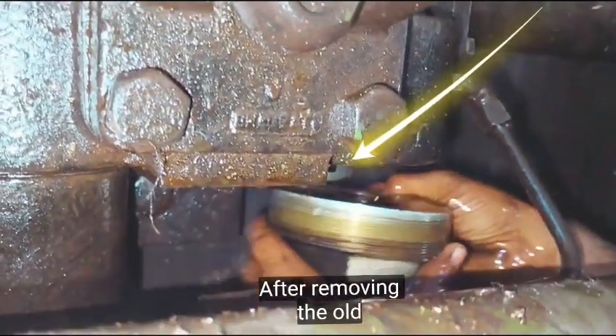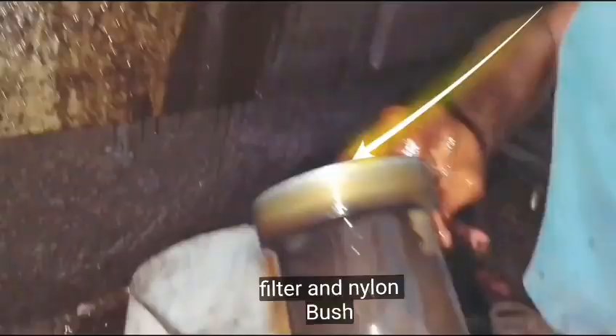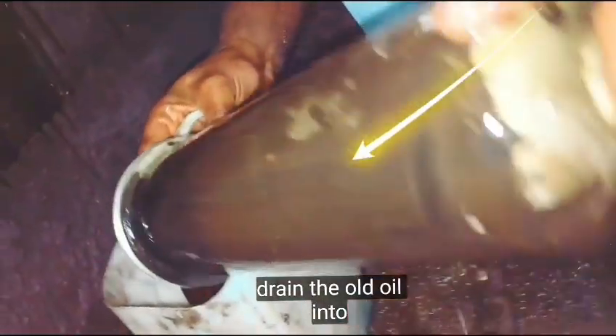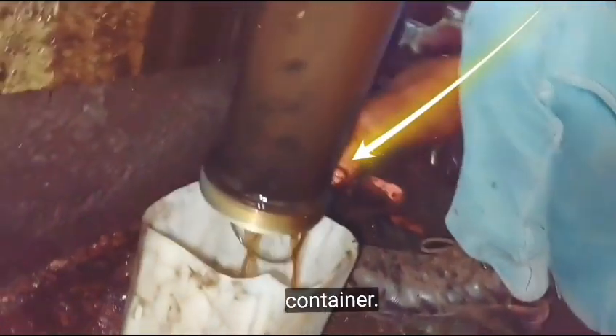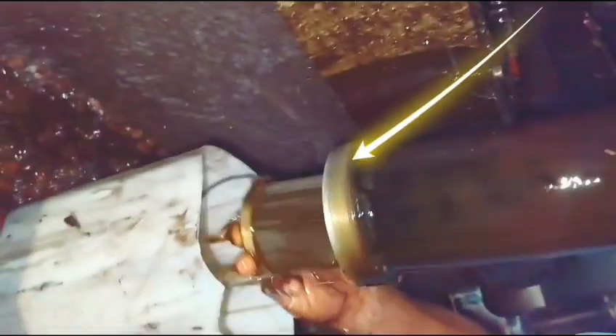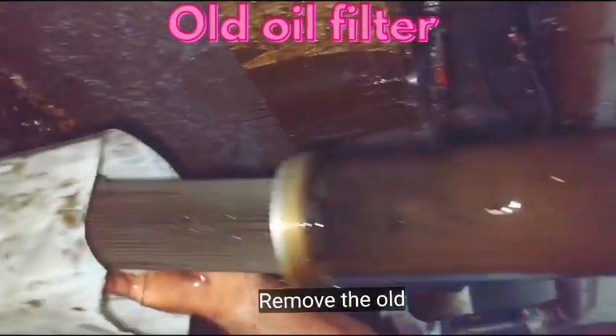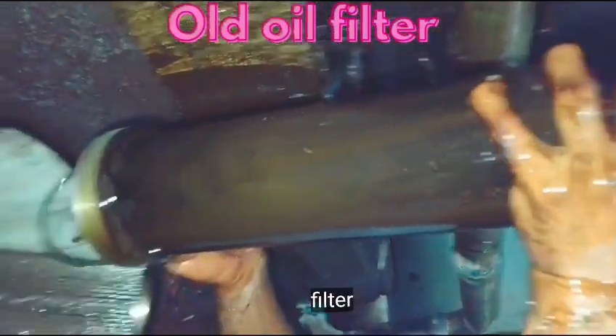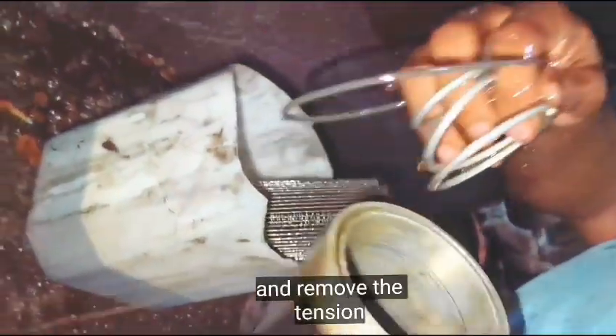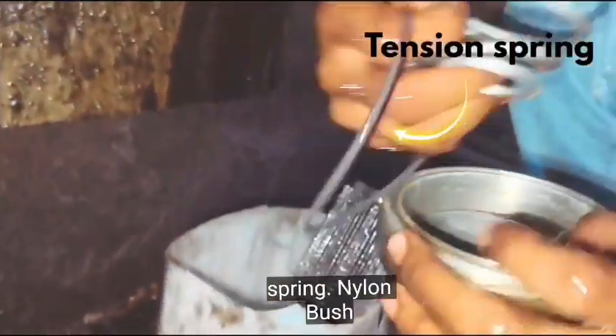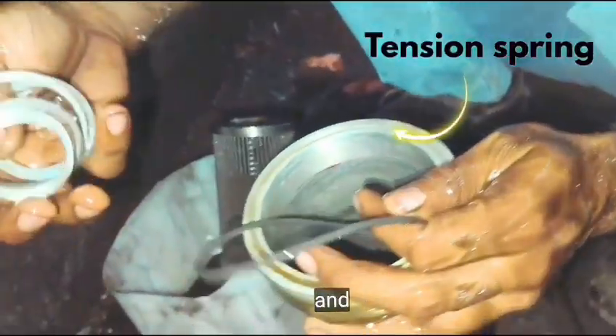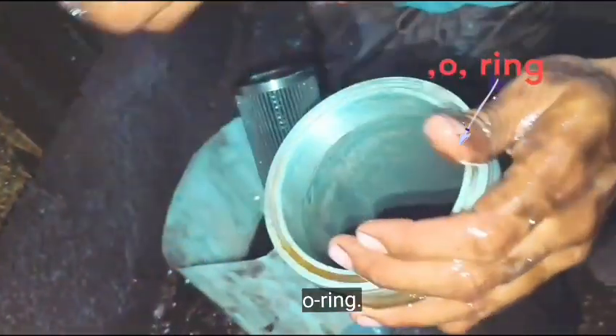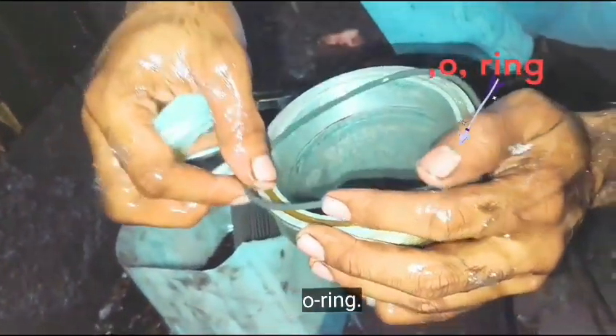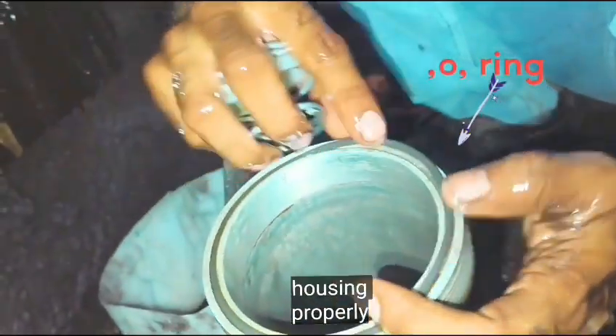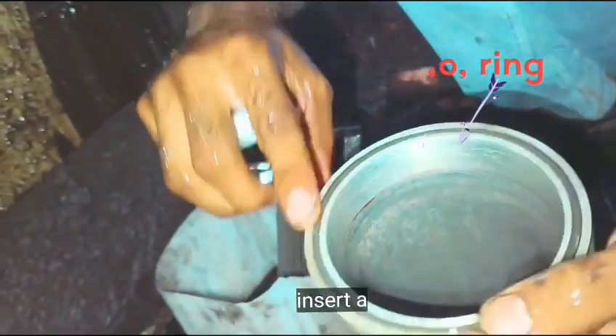After removing the old filter and nylon bush, drain the old oil into a container. Remove the old filter, and remove the tension spring, nylon bush and o-ring. Clean the filter housing properly. Insert an o-ring.